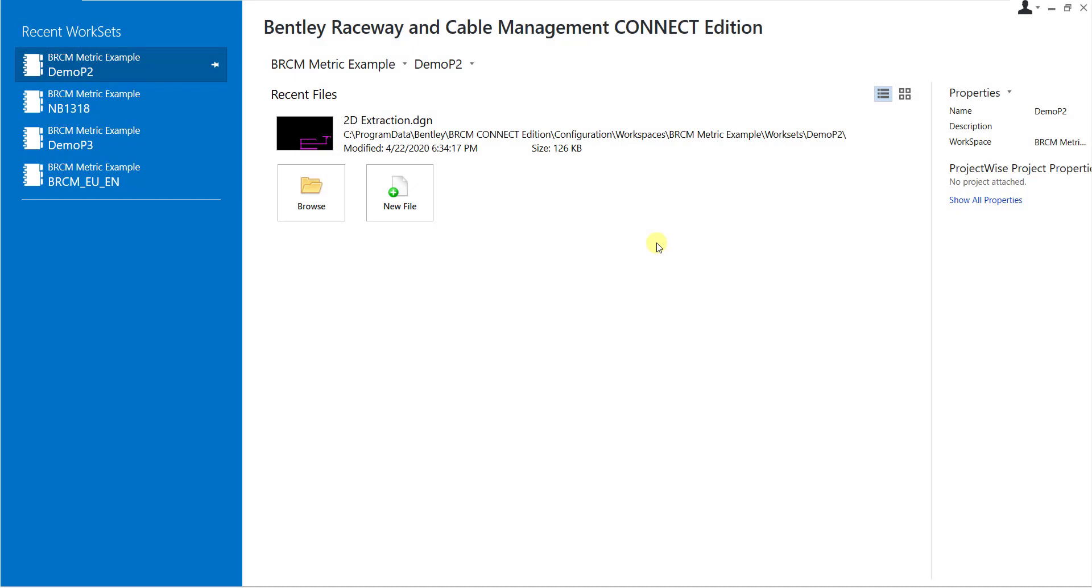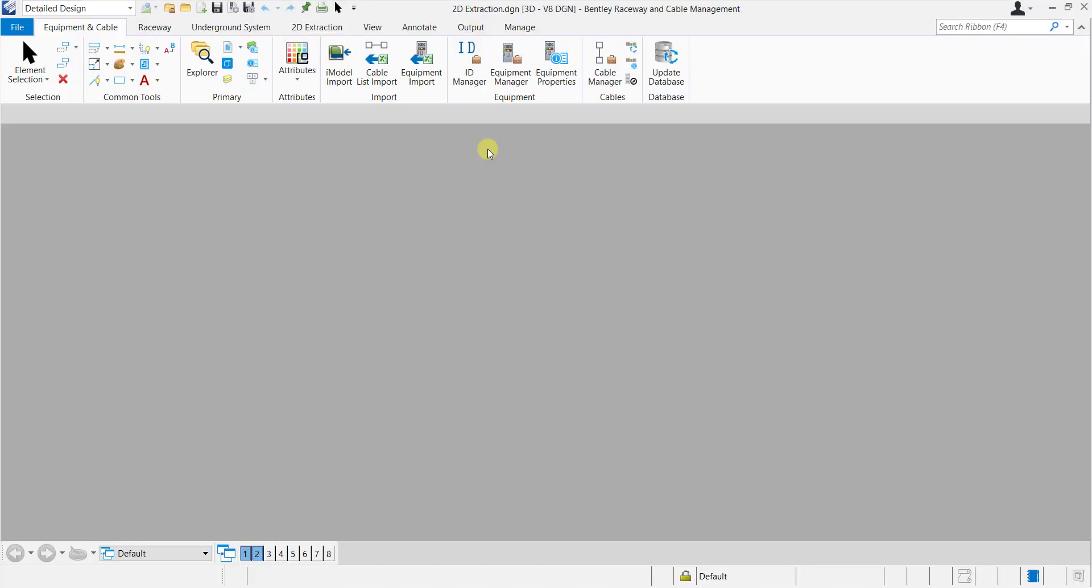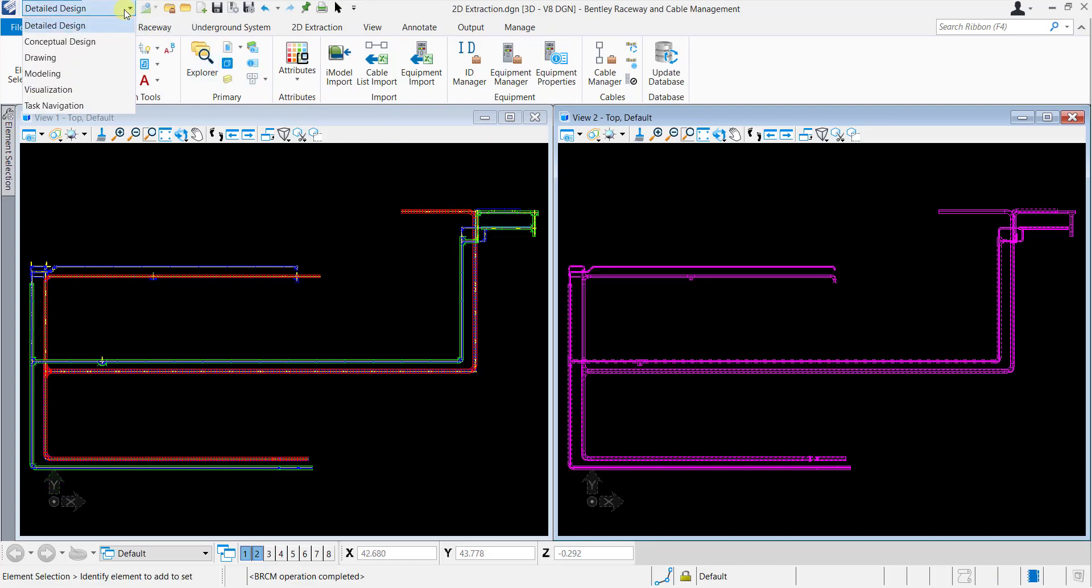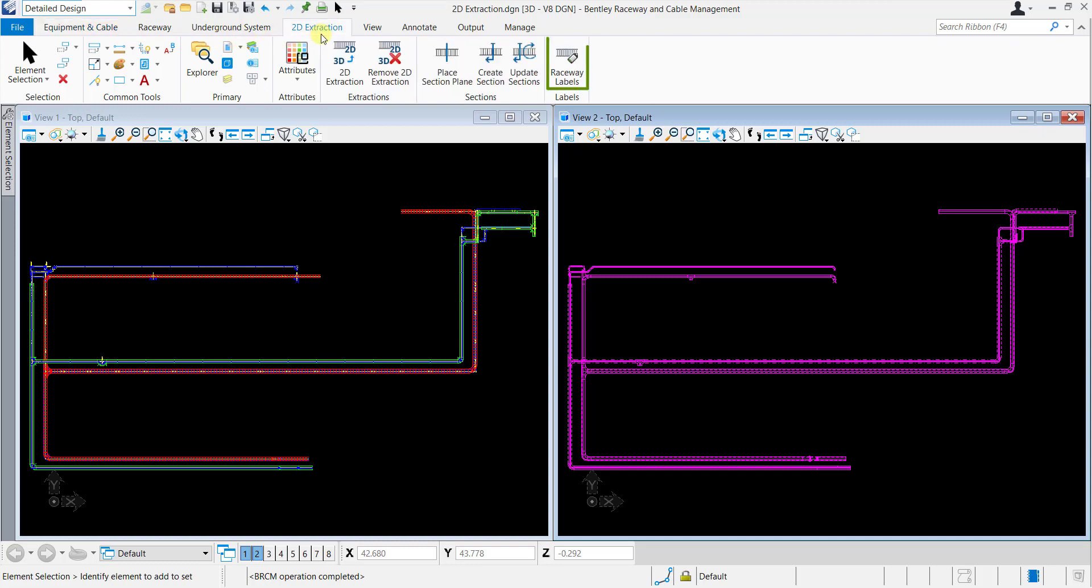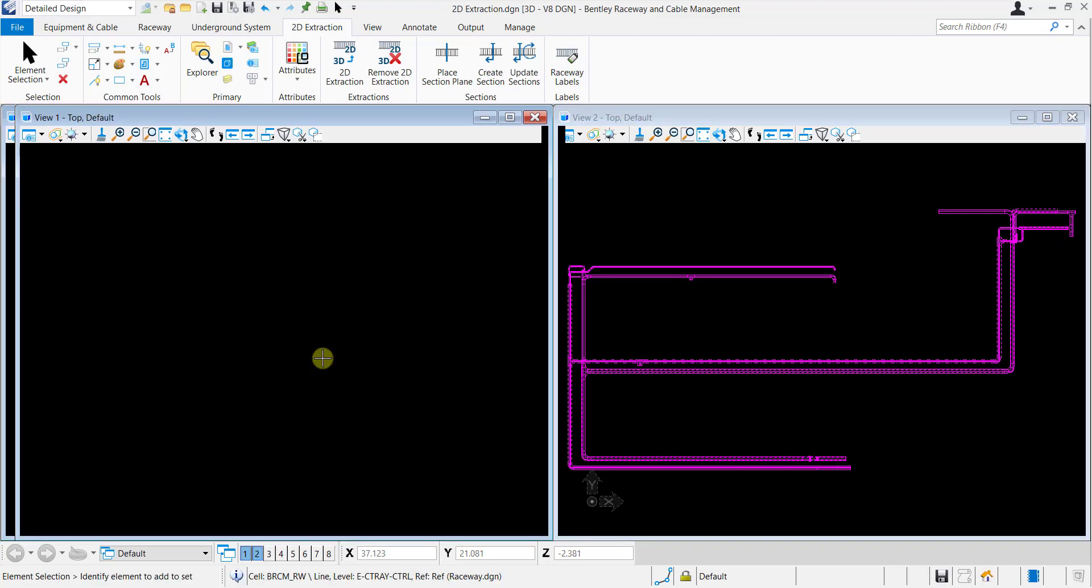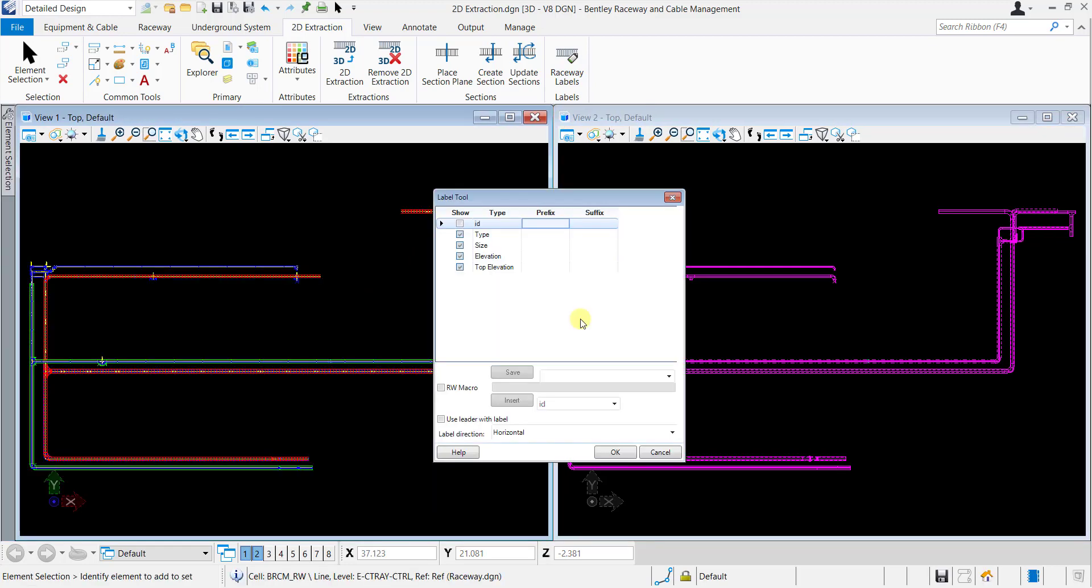Launch Bentley Raceway and Cable Management and open 2D Extraction Drawing. Select the Detailed Design Workflow and under 2D Extraction ribbon tab, select Raceway Labels from the Labels ribbon group. Select the Raceway system for which you want to place a label. The Label tool dialog will open.